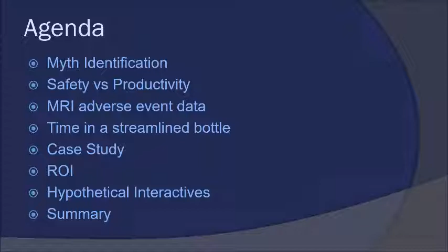MRI poses some unique safety concerns. Almost everyone is aware that MRI scanners are essentially giant magnets. What they may not know is that in most cases, the magnet is always on. There might be a misconception that if the tech is not available, if we're not taking care of a patient, if a patient's not in the bore of the magnet at any given time, that the magnet is not on, meaning it's not energized. This is rarely the case anymore. This means that the potential for projectiles is always of great concern. What we may not realize is that the impact the magnetic field may have on medically implanted devices in foreign bodies is always on as well.